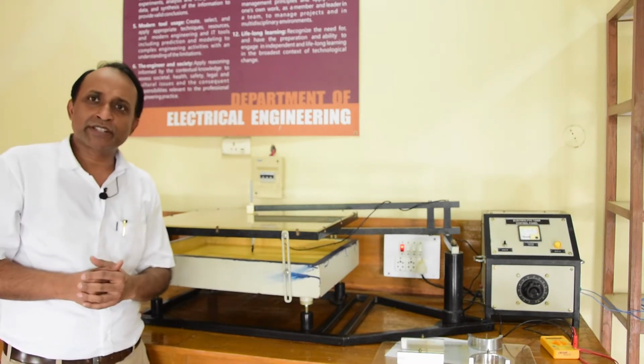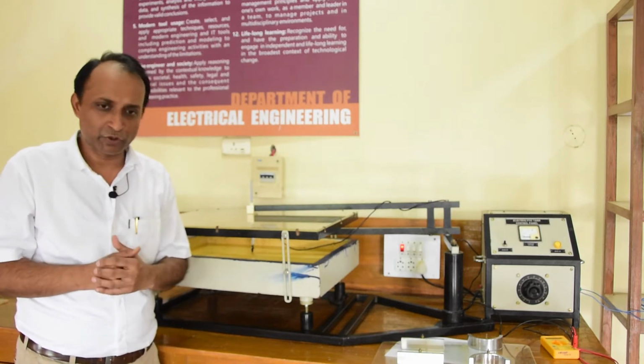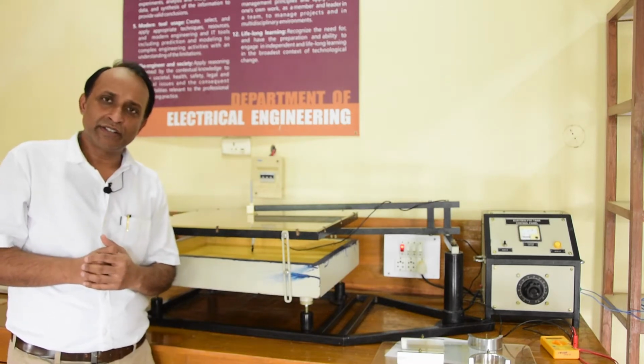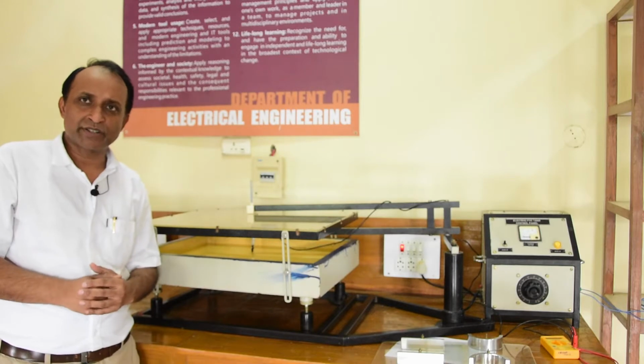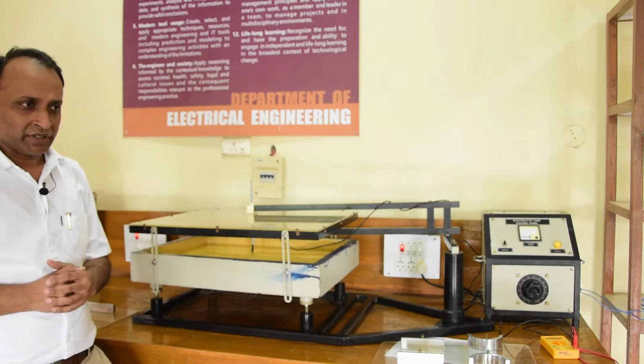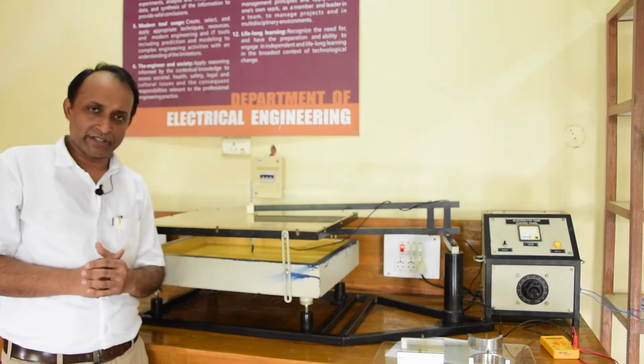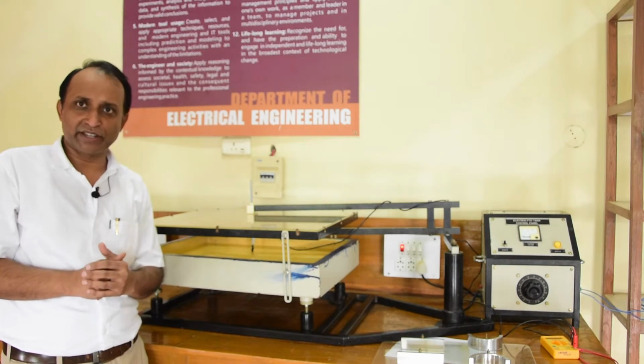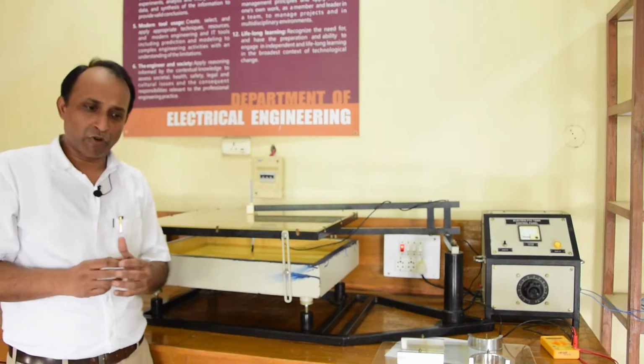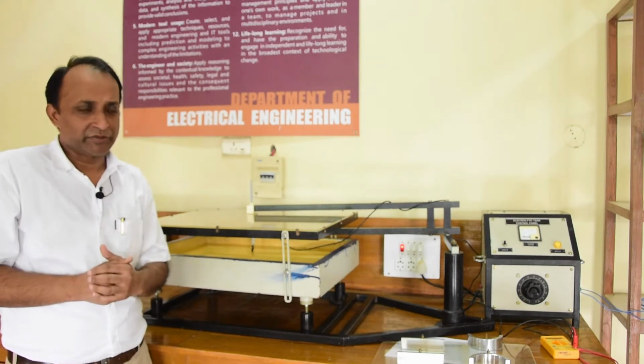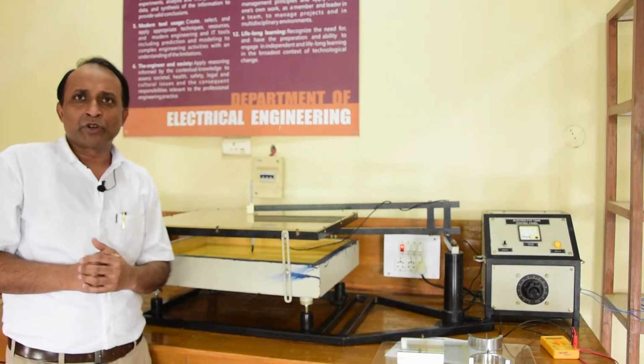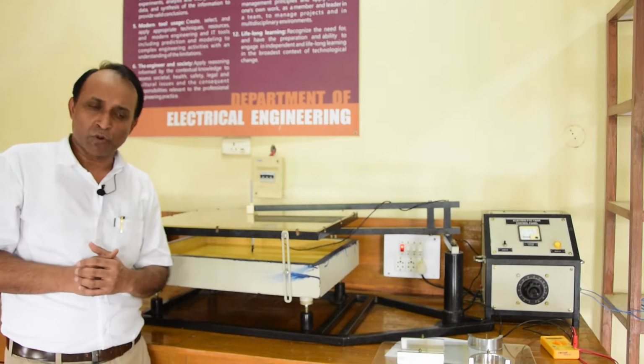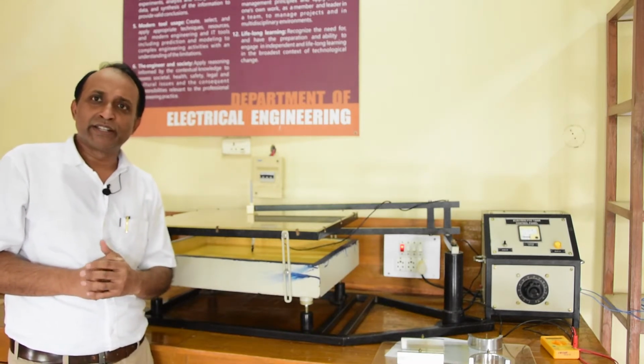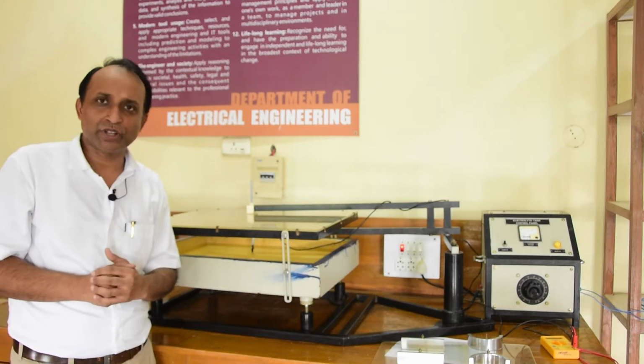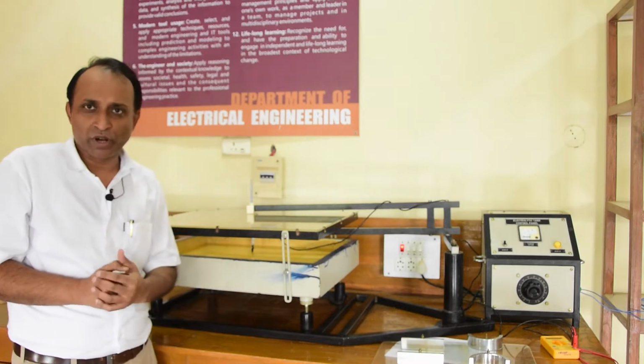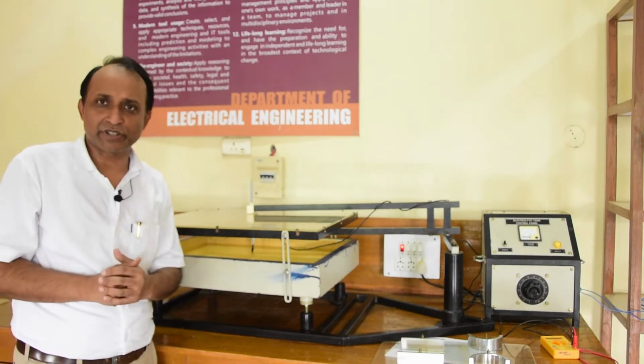At high voltages, the intensity of electric fields is so high that it tends to ionize the surrounding air and nearby objects. So in all high voltage electrical apparatus, care has to be taken in selecting the type of electrodes, terminal leadouts, and their physical dimensions and structure, because if this is not selected properly, the intensity of the electric field may produce harmful effects, such as corona near sharp or pointed edges.